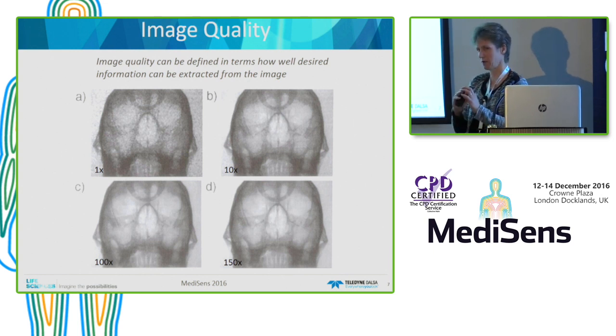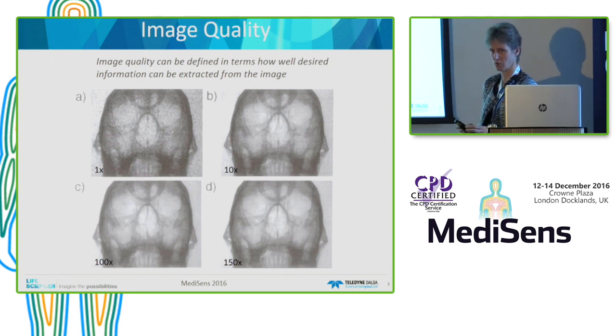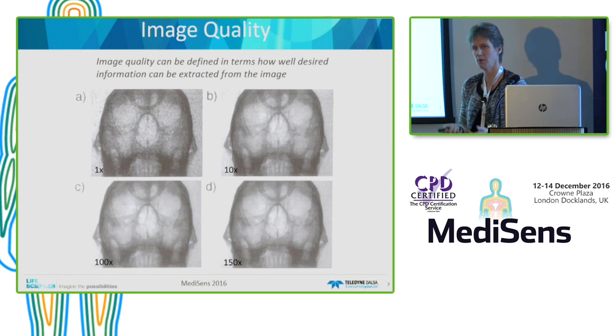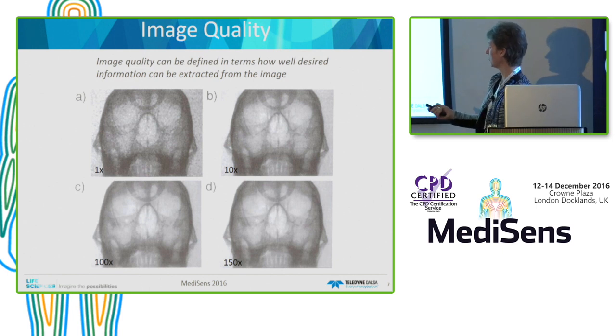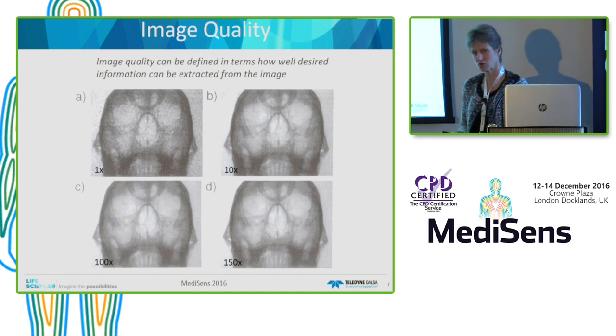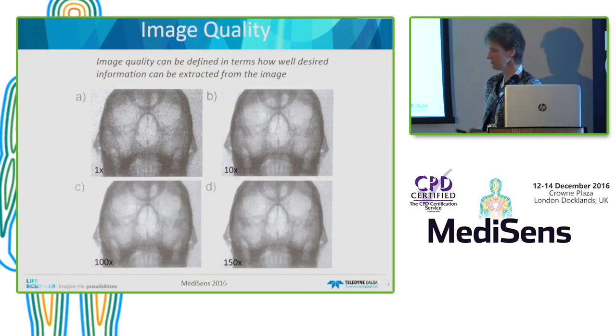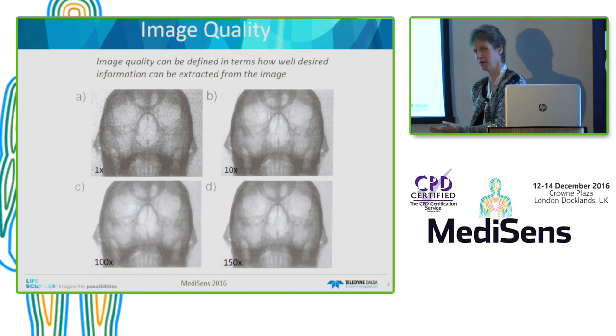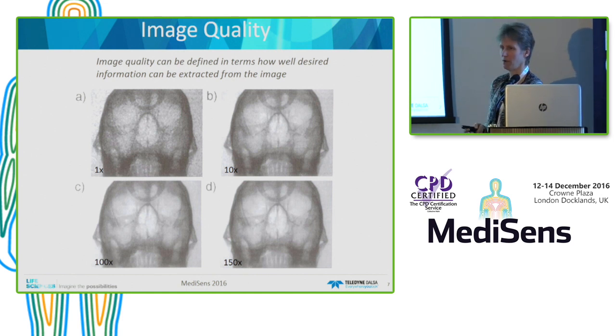What you see here is the statistical nature of photon shot noise. The image looks very noisy, but that is due to the photon shot noise — not due to a poor detector. If you start to increase the dose you start to observe more details in the images. Comparing these two images, you still see slightly more details at higher dose. Whether that detail is clinically interesting, I'm not the expert to answer, but the more dose applied, the better the image quality — though it's worse for the patient and medical personnel.